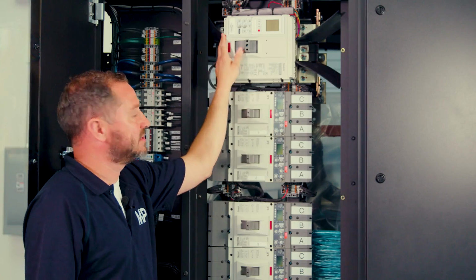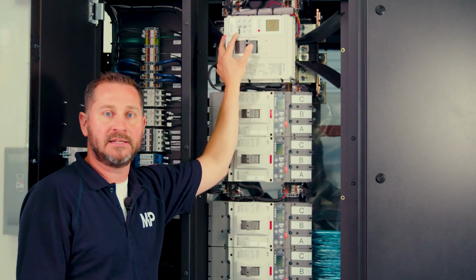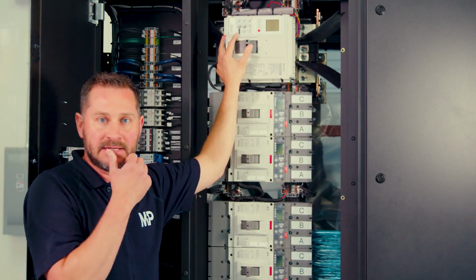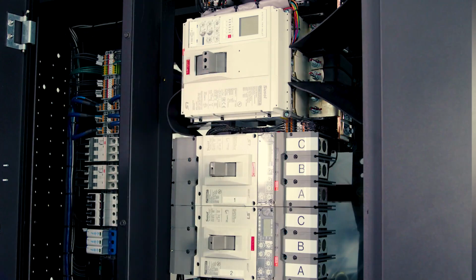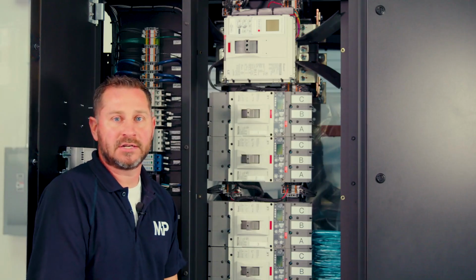Our main breaker is set at 600 amp because we have it tapped at 415. So that's 696 amps capacity. So 600 amp is plenty for that. Next, we'll jump over to our control section and check that out.